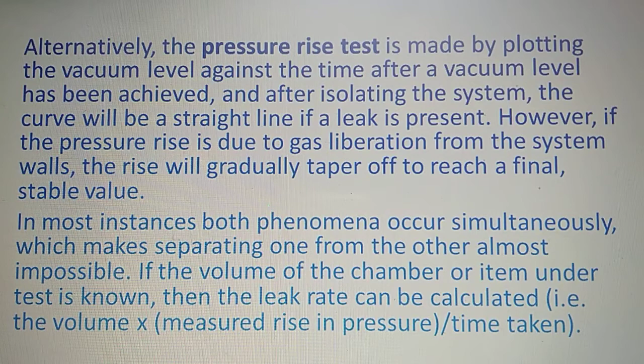Let's go for the next kind of test, that is the pressure drop test. This test is not dissimilar to the pressure rise test. It is only rarely used to check for leaks in vacuum systems, and only when the gauge pressure does not exceed 1 bar, since the flange connections used in vacuum technology will not tolerate higher pressures.